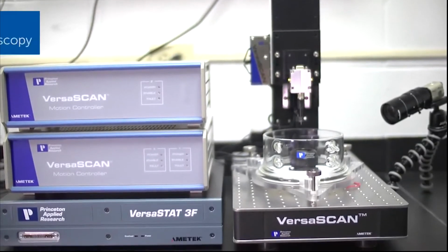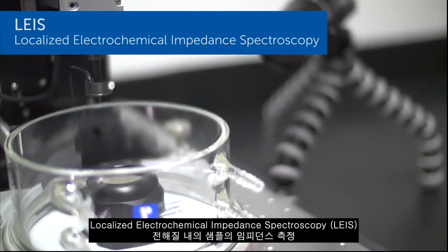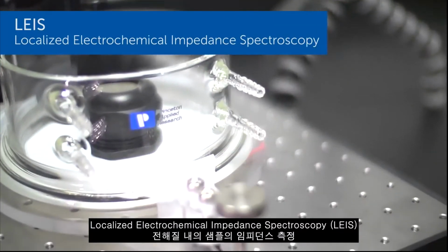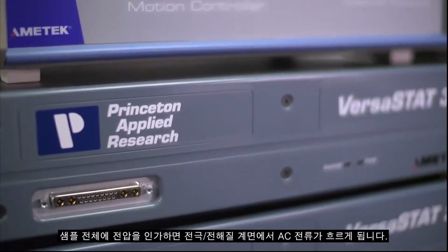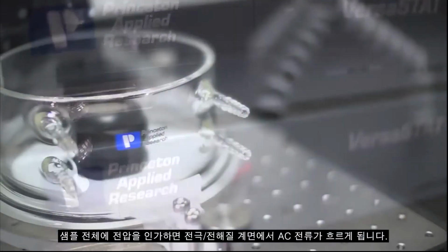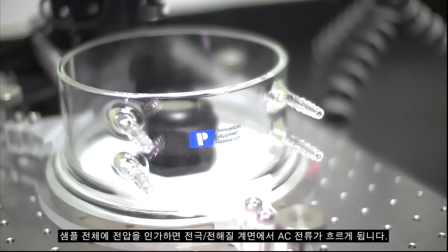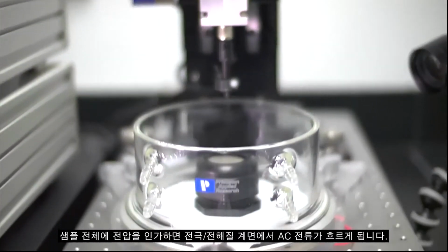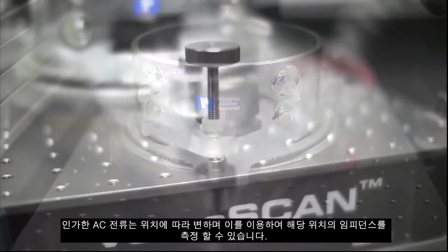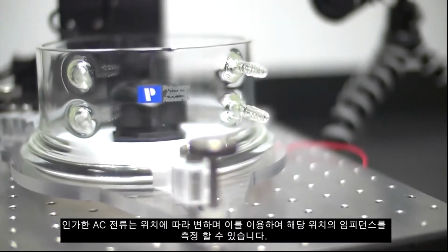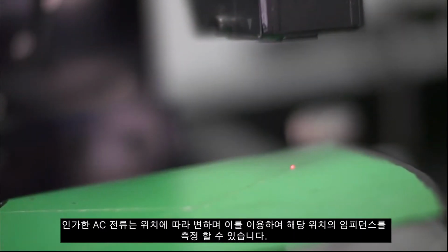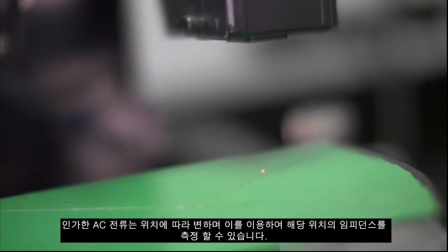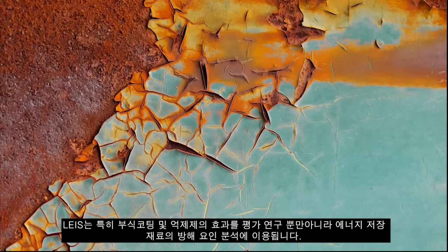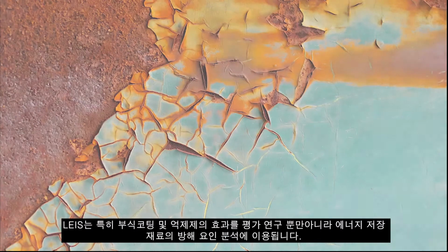Localized Electrochemical Impedance Spectroscopy, LEIS, employs the Princeton Applied Research VersaStat 3F to apply an AC voltage to the sample immersed in electrolyte. The global voltage causes AC current to flow at the electrode-electrolyte surface. This AC current varies spatially, allowing the determination of local impedances. This technique is particularly valuable in the evaluation of coatings and inhibitor efficacy in corrosion studies, as well as failure analysis of energy storage materials.